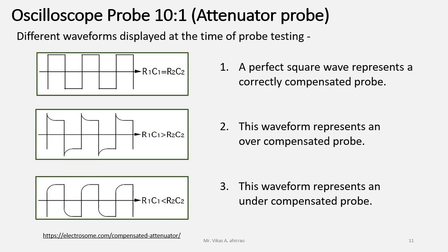So, when we have to test the probe and use it, we must get a correctly compensated probe. That is, at the time of probe testing, we should have a perfect square wave. And if we are getting the waveforms like shown here, as in figure 2nd and 3rd, then we have to adjust the trimming capacitor till we will get a perfect square wave.